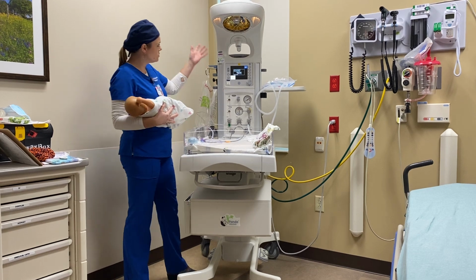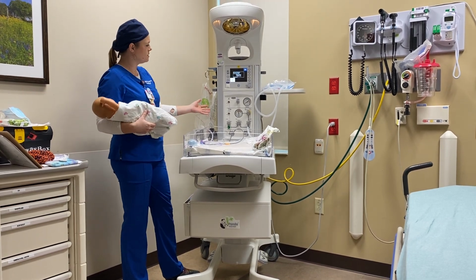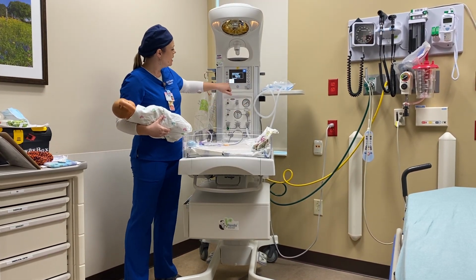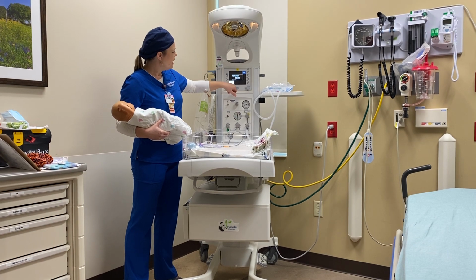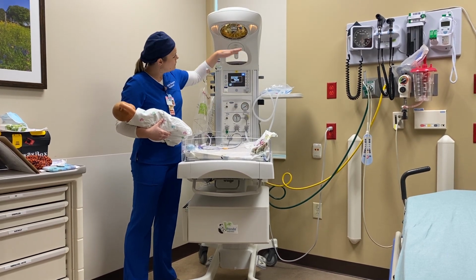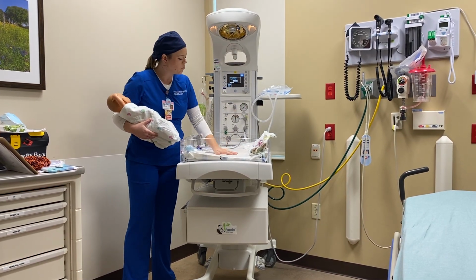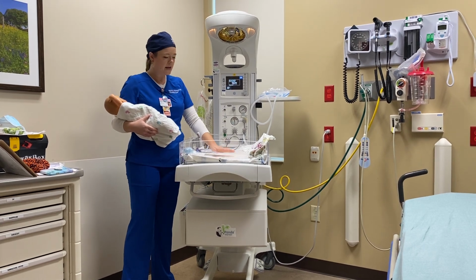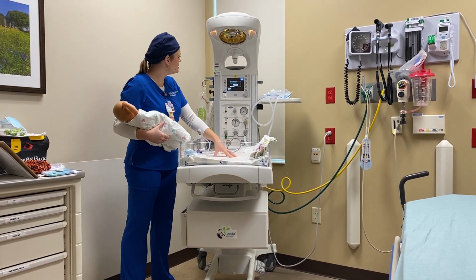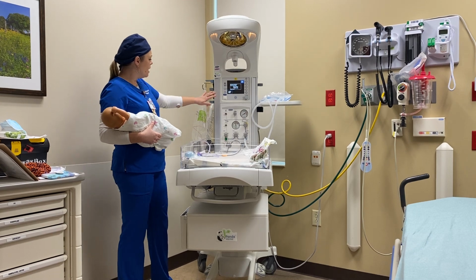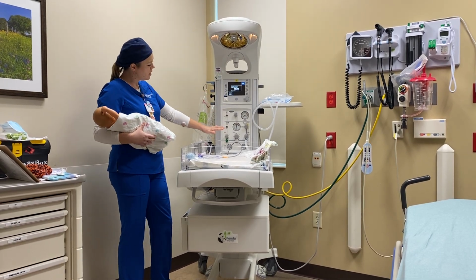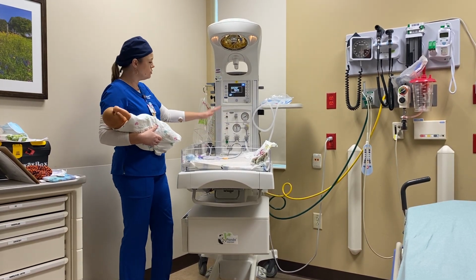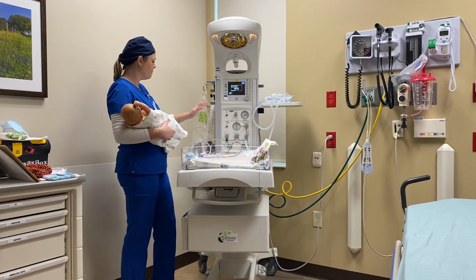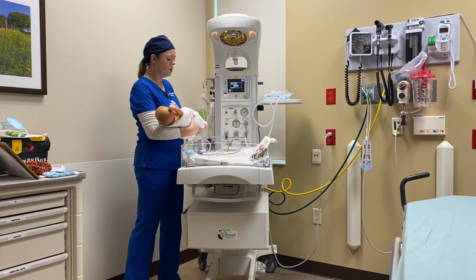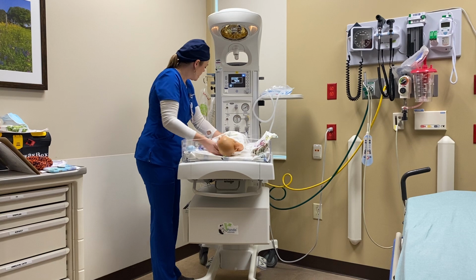So to start, this is what the bed should look like at all times. You leave it on, it's blinking admit baby. This is giving you a base level of 50% heat, so your bed is warm, and that's extremely important for a stable baby. So your bed is heated, and then all of your equipment here can stay off until the need for resuscitation, but you do want to check it. If you know you have a delivery coming, you need to make sure everything is operational. So we're going to check our bed now.